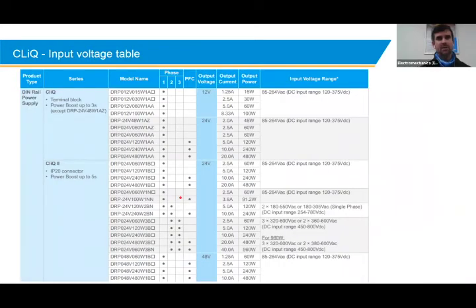So looking at the input voltage table for the CLIQ and the CLIQ2 series, you'll note that CLIQ is only single phase input. And then when we get to our CLIQ2 range, the three-phase versions, we have 2 and 3-phase operation. So if you buy a 3-phase power supply from us, you don't necessarily have to supply 3 phases to it. You could supply 2-phase 400 volt. And instead of a 3-phase breaker, use a 2-pole breaker, and obviously save a little bit in that sense as well, and in your wiring time. So the CLIQ2, as noted here, they are capable of 2-phase as well as 3-phase operation.